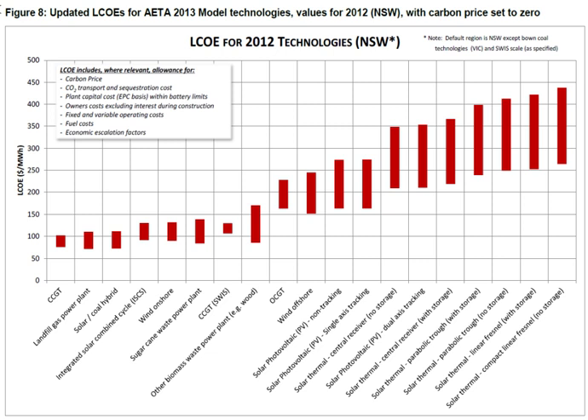Fuel costs are high for fossil fuel and biomass sources, low for nuclear, and zero for many renewables. Fuel costs can vary somewhat unpredictably over the life of the generating equipment due to political and other factors. Works power, own use or parasitic load — the portion of generated power actually used to run the station's pumps and fans — has to be allowed for. To evaluate the total cost of production of electricity, the streams of costs are converted to a net present value using the time value of money. These costs are all brought together using discounted cash flow.